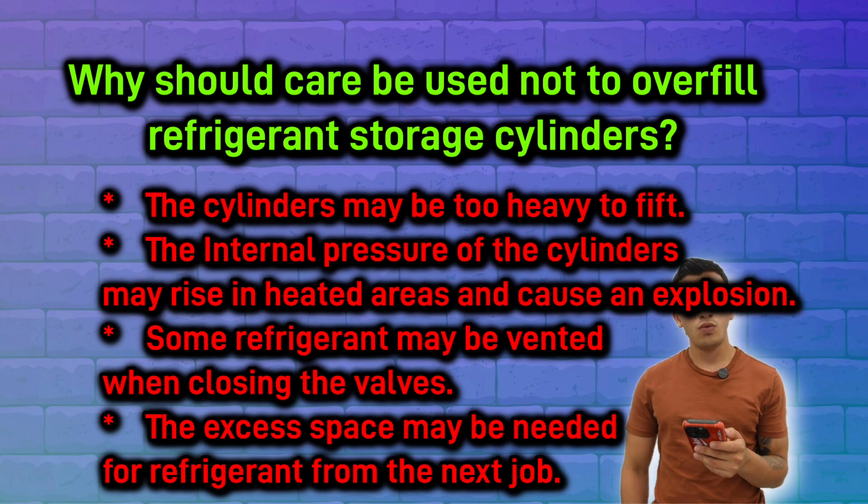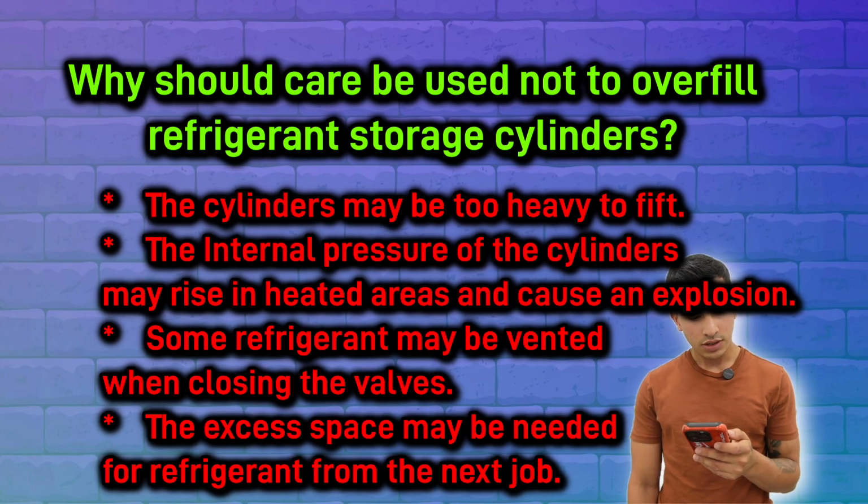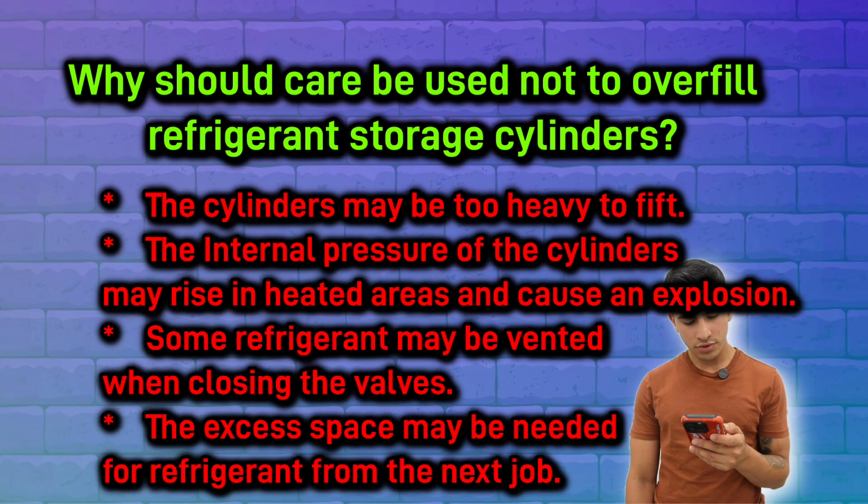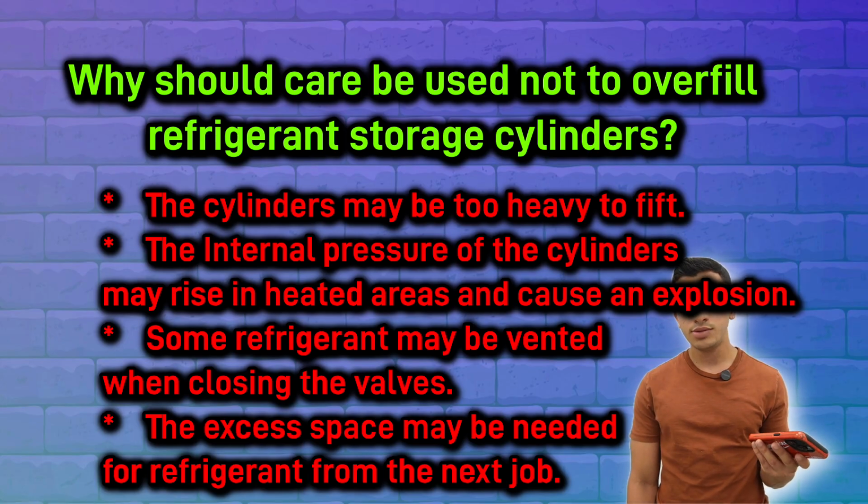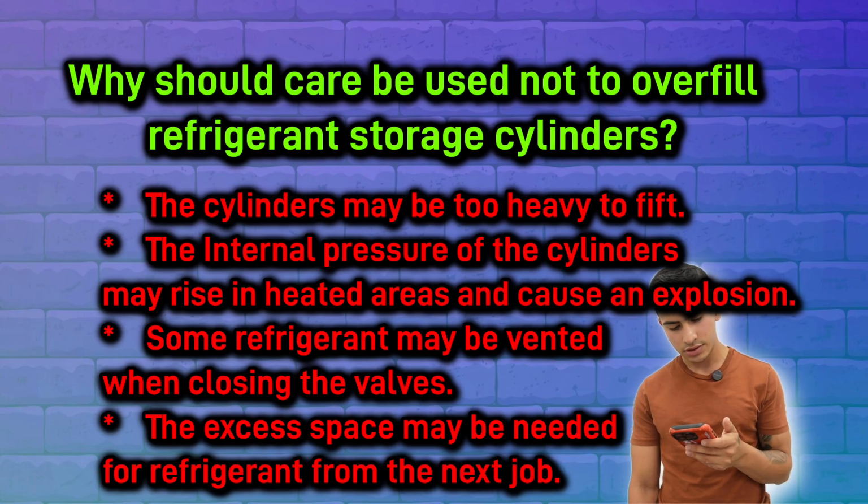24. Why should care be used not to overfill refrigerant storage cylinder? So 24. Why should care be used not to overfill refrigerant storage cylinder? It's kind of obvious. You just want to fill it up to 80%, only 80%. You never want to go above 80%.